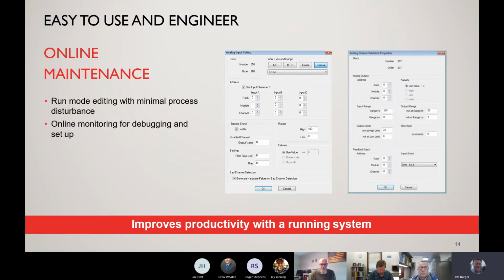You can do this in runtime mode, so you can add your function block, you configure it, and then once you save it and download to the CPU, it'll actually give you a choice between either hot start or cold start. For a hot start, it will take your configuration that you changed, it will store it into memory, and then on the next scan, it will actually put that new control algorithm in run mode and will not allow the CPU to shut down.